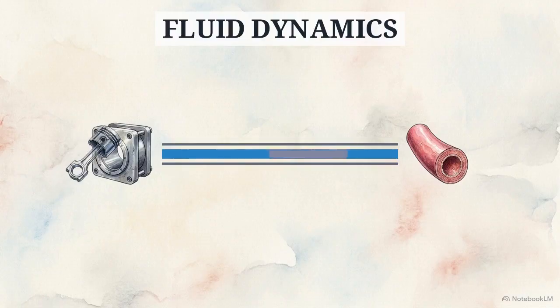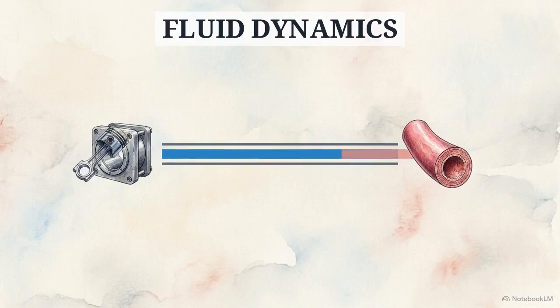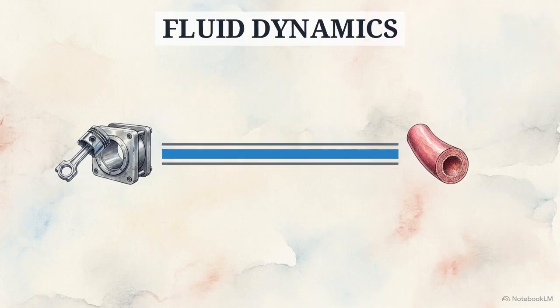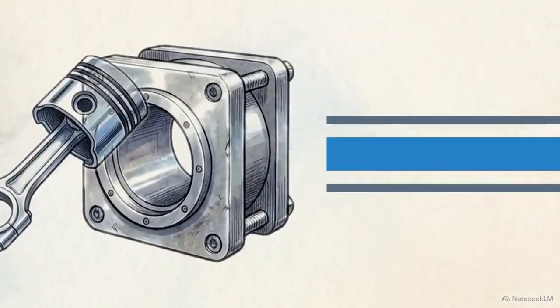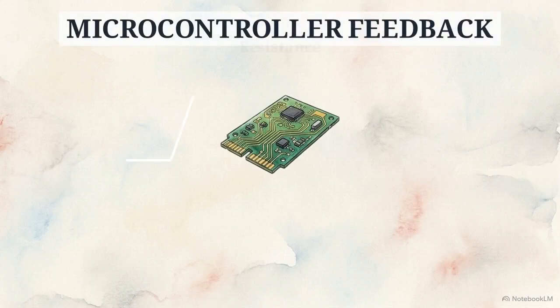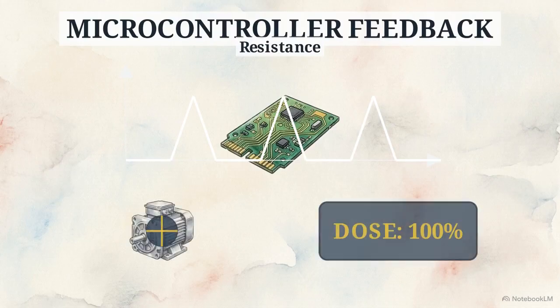This is perspective 2, engineering. The physics challenge is that the pump isn't pushing fluid into an empty pipe. It is forcing liquid against the dynamic, rhythmic back pressure of a living patient's circulatory system, which is constantly pushing back. Zooming inside the pump mechanism reveals perspective 3, electronics. To overcome that biological resistance, internal sensors constantly measure the flow rate and feed that data to microcontrollers, which carefully drive a stepper motor to maintain the exact dose.